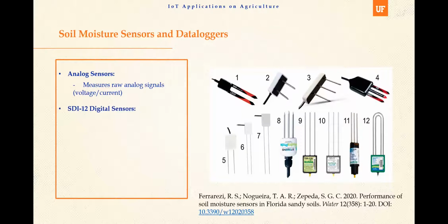SDI-12 is a standard communication protocol that transfers measurements taken by an intelligent sensor to a data logger. An intelligent sensor is a microprocessor-based sensor, like a little computer, that typically makes computations based on the raw sensor reading and outputs the measured data in engineering units by itself.